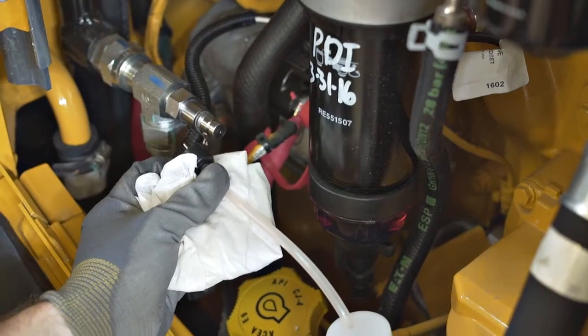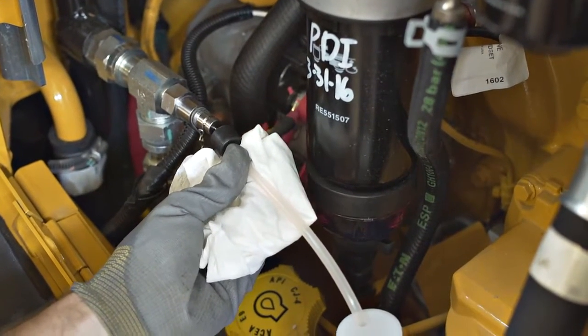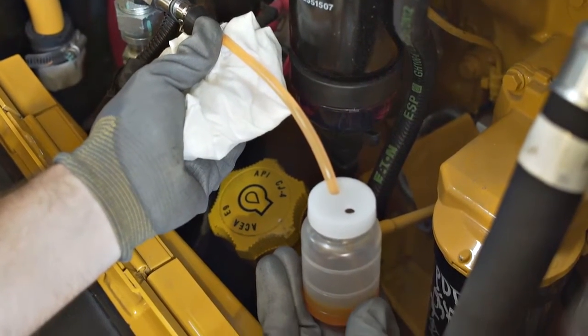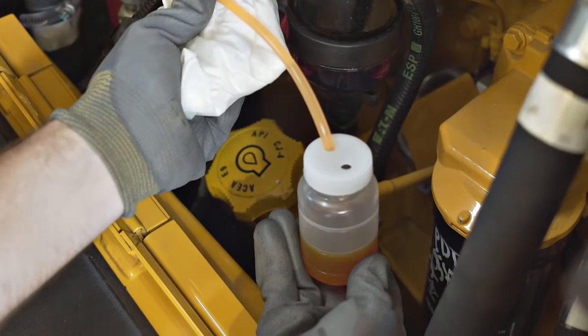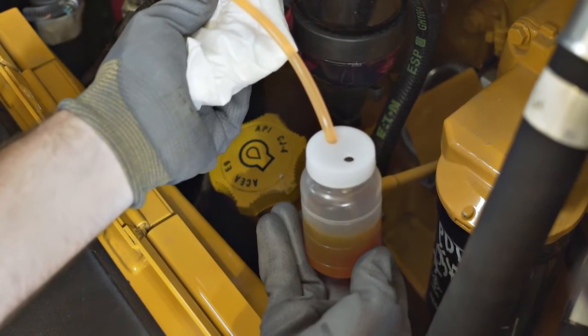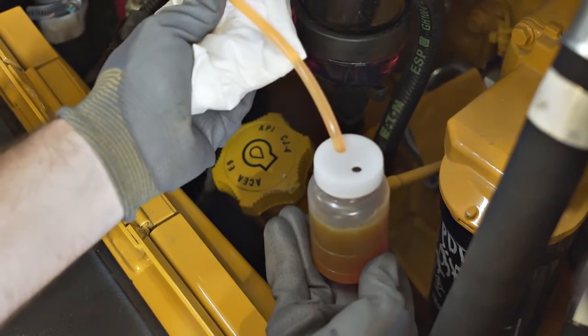To take the sample, press and hold the sample probe to the valve to release oil from the system into the sample bottle. Fill the oil sample bottle approximately 80% to 90% full. Leave some air space between the top of the fluid and the top of the bottle.